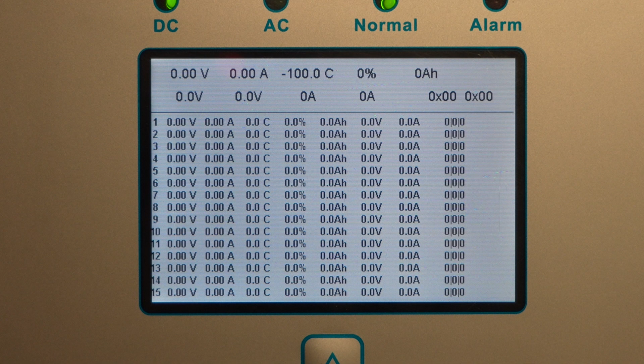The other thing to look at here is the lithium battery page. If you're plugged in with a communication cable, you should be showing this page. If your communication cable isn't showing, or you have the wrong communication, then this is the page that will come up. But provided we come up with that page, then they're talking to each other. So here we've got some interesting figures. All of this is just obviously reading straight off the battery. There's nothing we can do about changing that. But these three, we actually can.